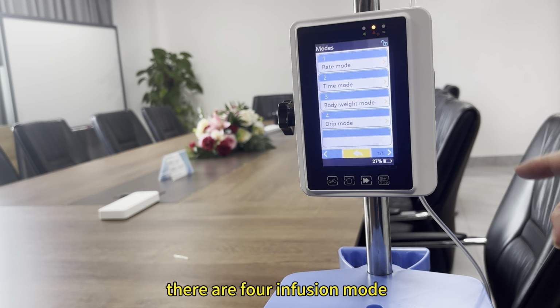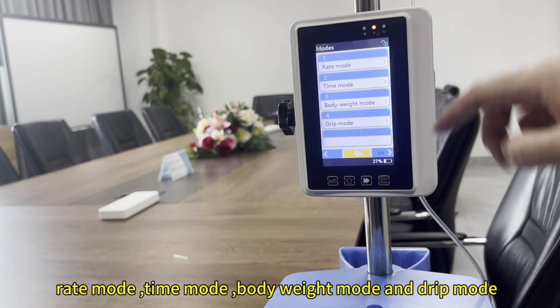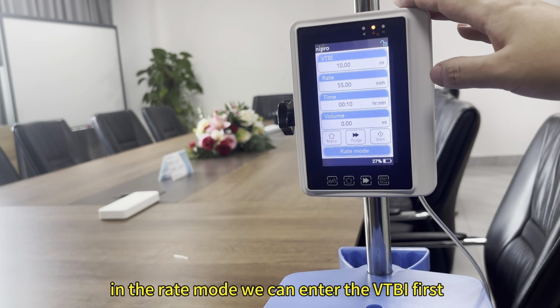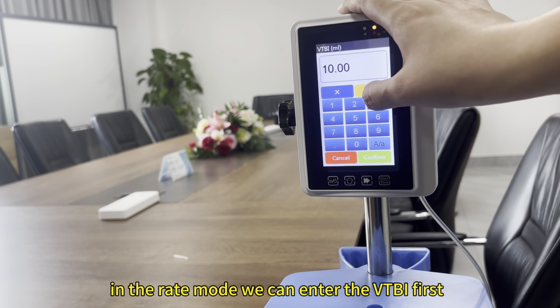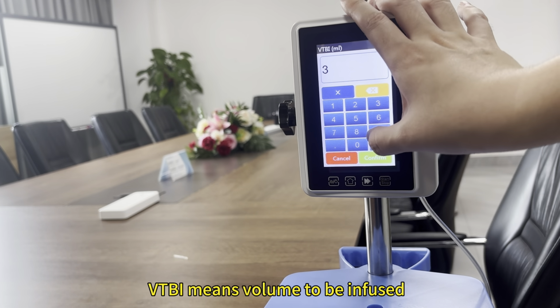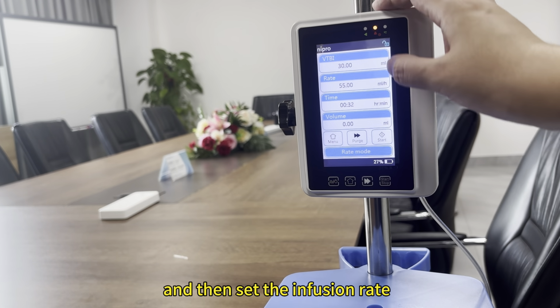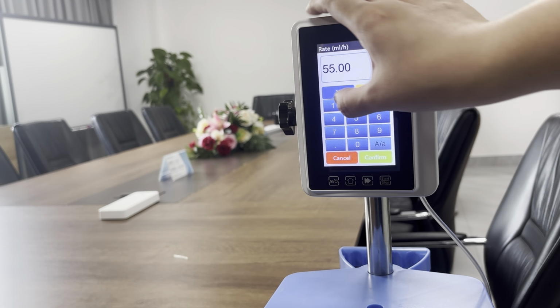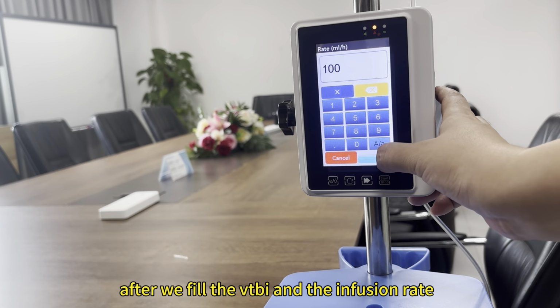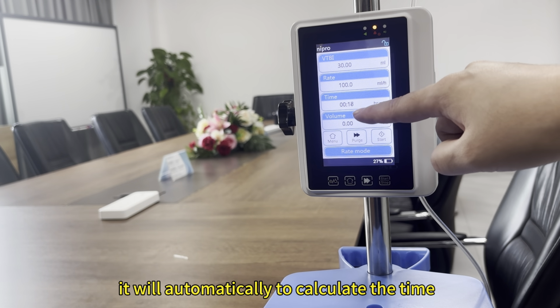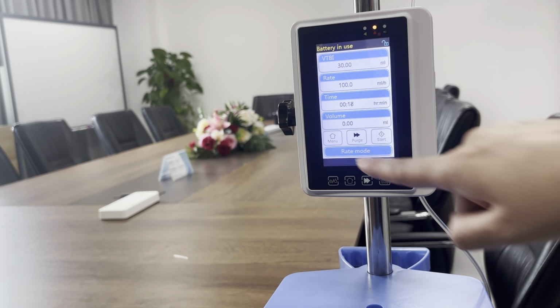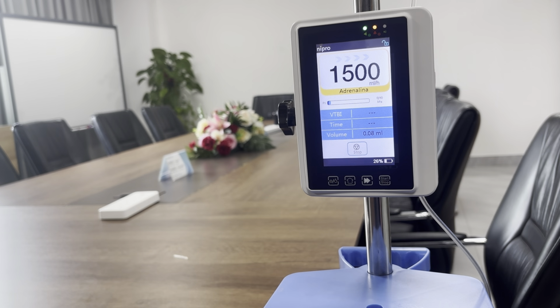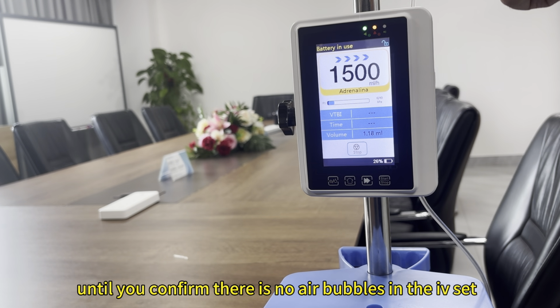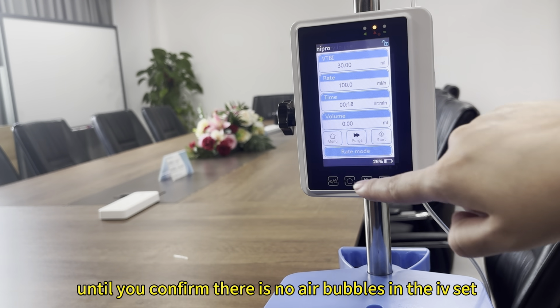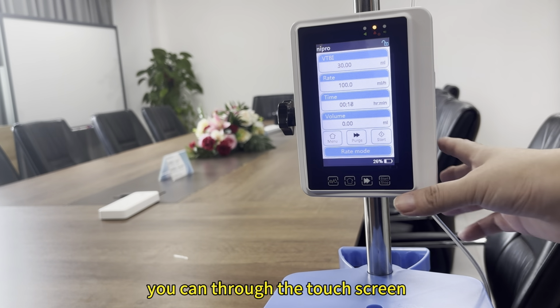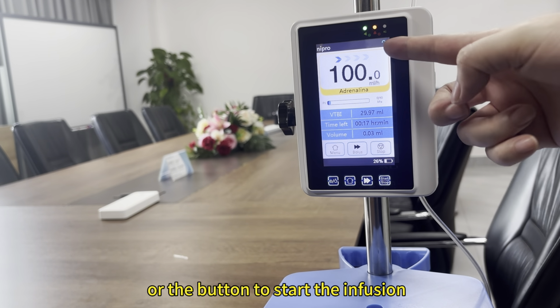There are 4 infusion modes: rate mode, time mode, body weight mode, and drip mode. In the rate mode, we can enter the VTBI first. VTBI means volume to be infused. Then set the infusion rate. After we fill in the VTBI and the infusion rate, it will automatically calculate the infusion time. Now we need to do the purge first, until you confirm there are no air bubbles in the IV set, and then we can stop the purge. You can touch the screen or the button to start the infusion.